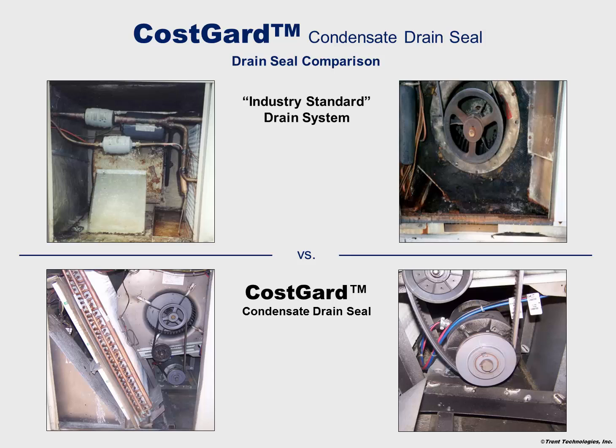These photographs compare the internal conditions of air handlers with and without the CostGard condensate drain seal. The differences are clear. The top photographs with the industry standard drain system were in operation for less than 10 years. Failed condensate drain systems led to these wet and dirty conditions, building damage and poor indoor air quality. In contrast, the bottom photographs show units that use the CostGard condensate drain seal operating for more than 13 years with no preventive maintenance. As you can see, the units are clean and dry inside, offering the owner many years of extended service.